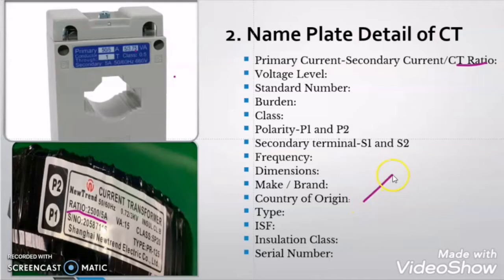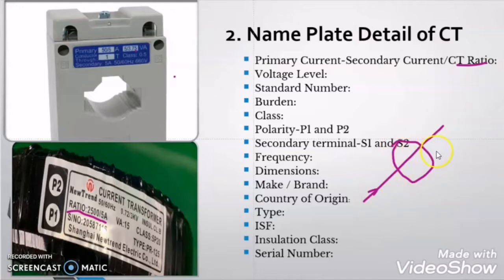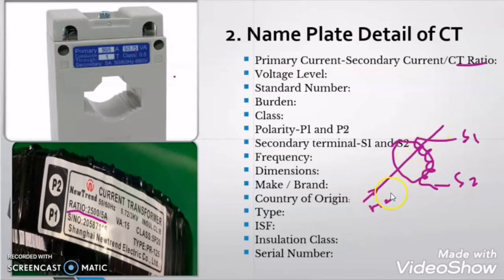As I told you, CT has only the secondary winding and the primary winding of the CT is that conductor whose current needs to be measured. So this is our CT and this is the conductor which is passing through the window of the CT. Here we have some secondary windings on the core of the CT and these are our terminals of the CT, that is S1 and S2. So here the primary winding turn is 1 because there is only one conductor, and suppose the turns in the secondary winding is 100.